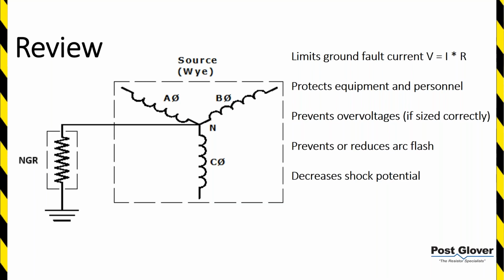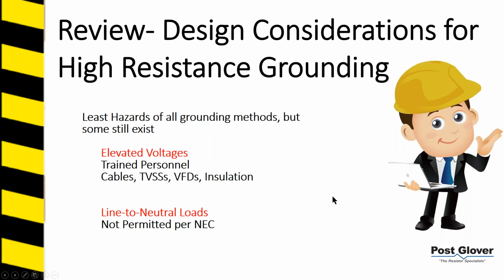Then it decreases shock potential from straight ground faults or straight ground voltages, excuse me. So let's talk about some design considerations for high resistance ground systems, since we're talking about that today. We're talking about elevated voltages. When you have a ground fault, no matter what it is, as long as you remain online you're going to have some imbalance in voltages. And for line-neutral loads, you're not permitted per the NEC on a resistance ground system to operate with line and neutral loads. So let's go into both of them a little more in depth.